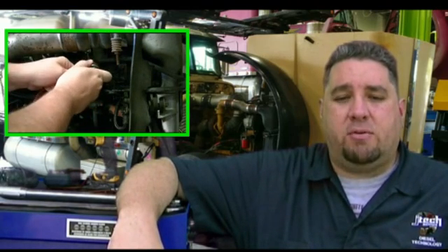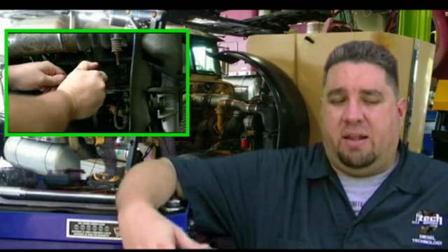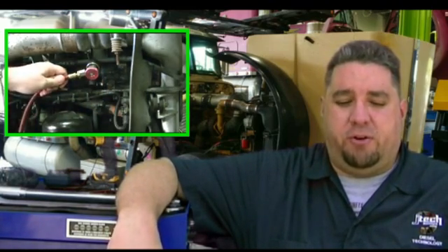After you've inspected everything, you want to make sure that the valves on the port connectors are set to open. You don't want to try to pull the collar back and attach the connector while the valve is closed, because it'll immediately start depressing the valve for the connector, and you'll start venting some of that gas. So make sure it's open before you clip it in place. Once it's clipped in place, then secure the valve down tightly, and that will depress and allow the pressure gauge to start reading the pressure.